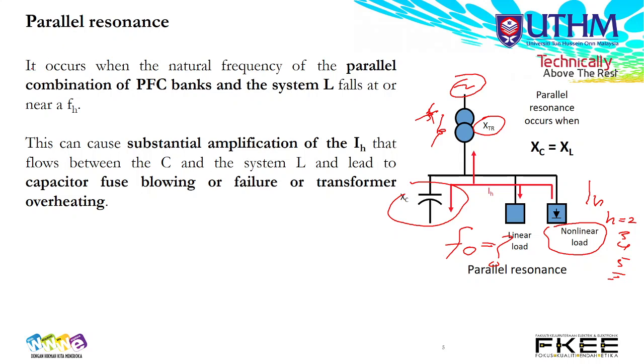This parallel resonance occurs when the natural frequency of the parallel combination of PFC, power factor capacitor bank, and the system L, meaning the inductance of the system, coincide. In this case, maybe we have the inductance of the generator.